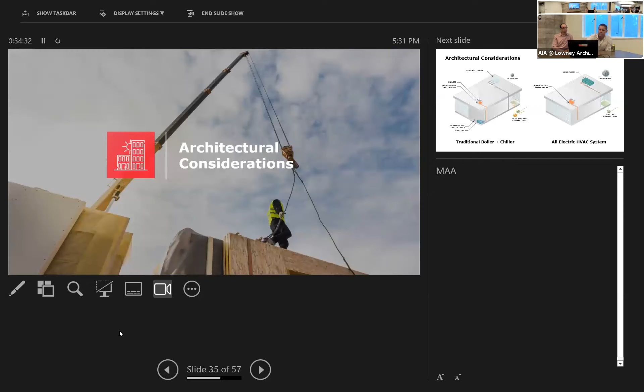Okay, some architectural considerations. We've got our traditional approach on the left, which is gas boiler, cooling towers, and water-cooled chillers, and on the right, we've got a building with air source heat pumps. The key thing here is that the air source heat pumps are quite big, bulky machines, so they'll typically take up more space than the cooling towers would have done. They're also pretty heavy, so there'll be more load imposed on the roof structure. And because they're refrigeration machines with compressors, they'll tend to create a bit of noise as well. So in noise-sensitive locations, if you've got a resi building next door, you've got to be really careful about locating the machines.